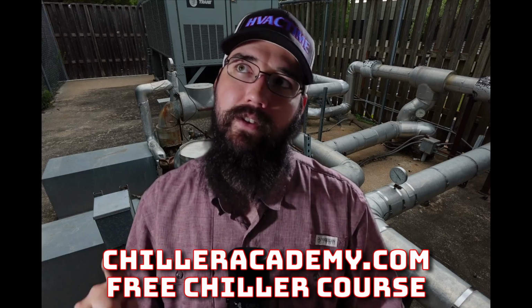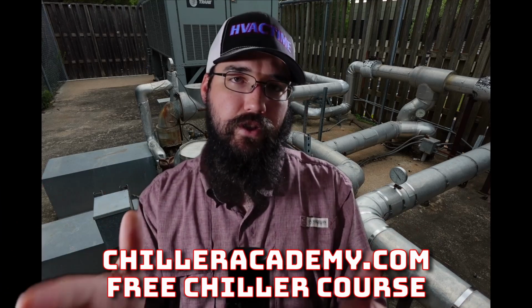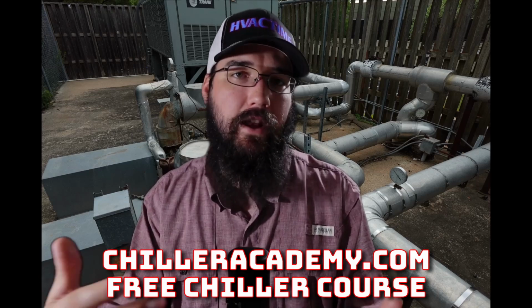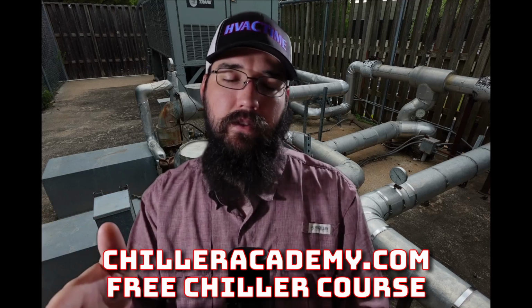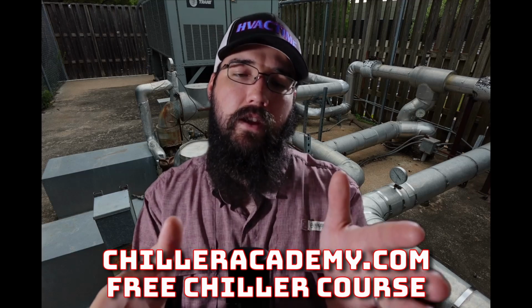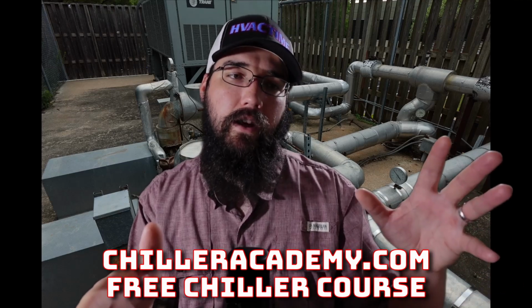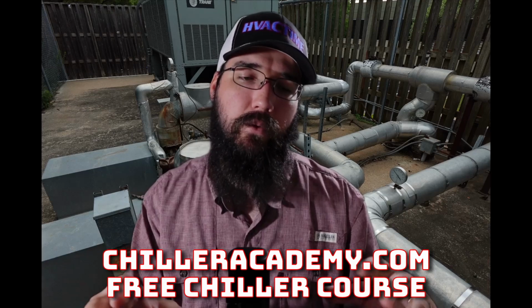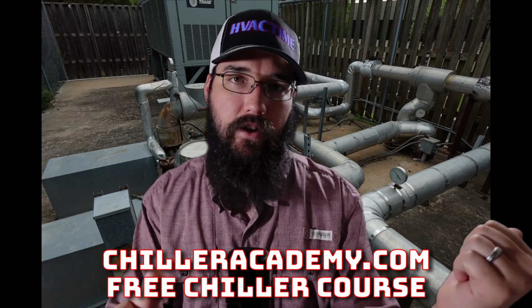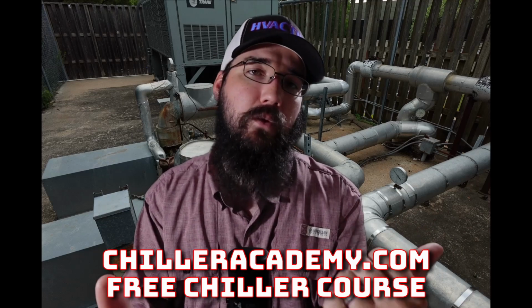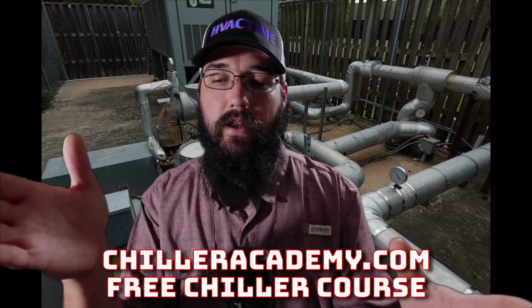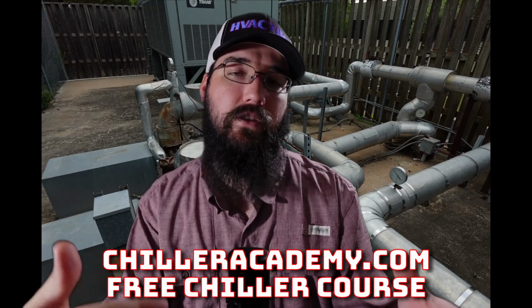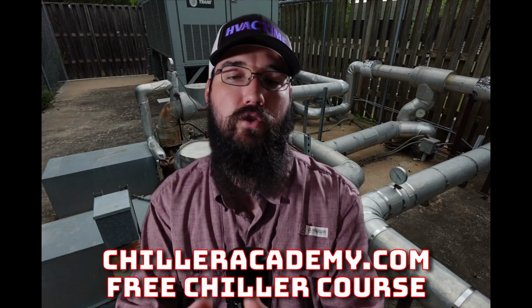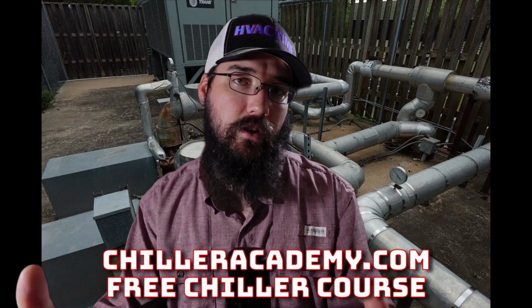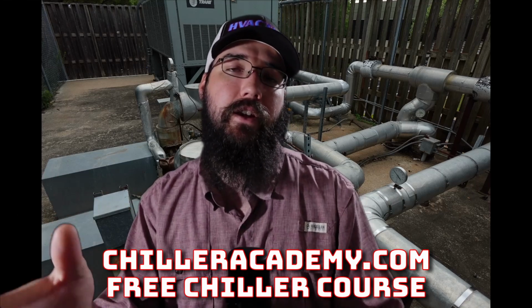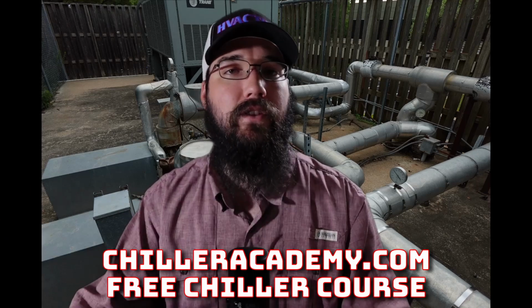If it's not sealed, which is the majority of our bearings, it'll have shields on it for protection, but they're not actually doing any other function for the most part. And so typically what that means is that in your bearing housing, the side of the bearing that faces away from the rotor and the stator, or that faces on the outward side, is maybe another way to say that in like a pump example. So if it's facing to the outer side, away from the center of the motor or the pump, that will typically be your bearing housing side, and that will not have a shield. The inner side will typically have its shield on there to help hold the grease. That's really its main function, is just grease retention. If you have blown shields, you're going to go through a lot more grease unnecessarily, because that shield is not there to help hold that grease and allow as much excess to sling out and make a mess everywhere.